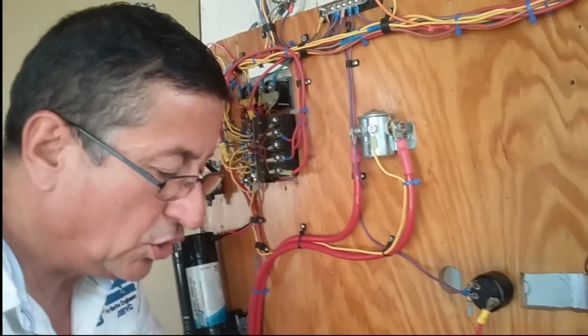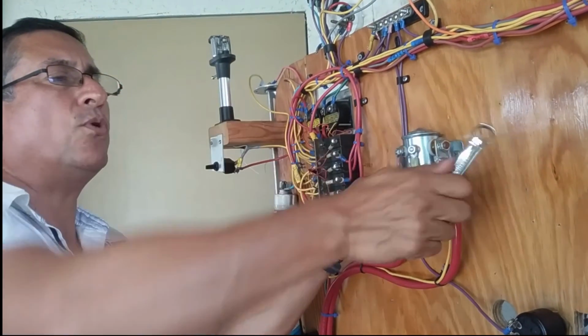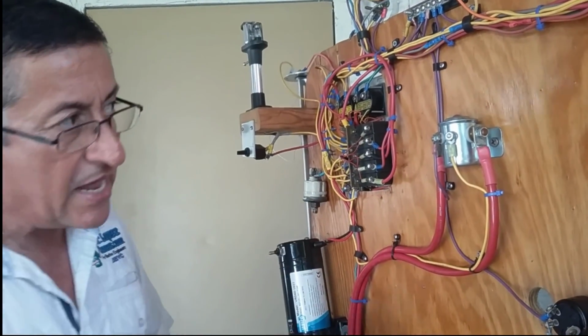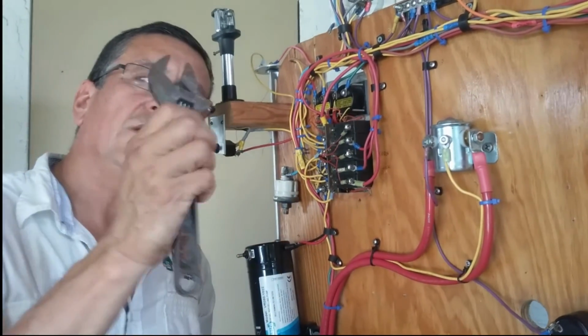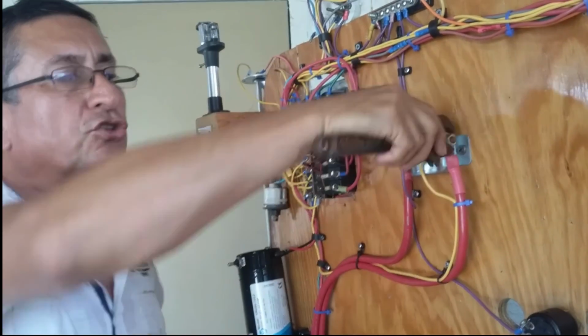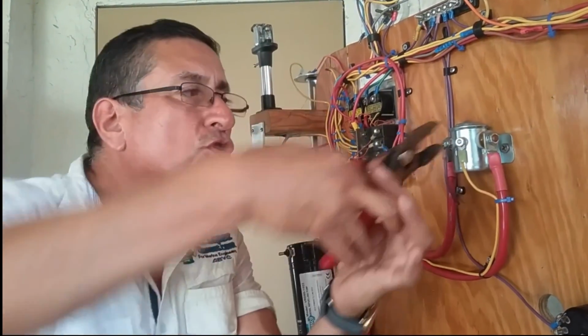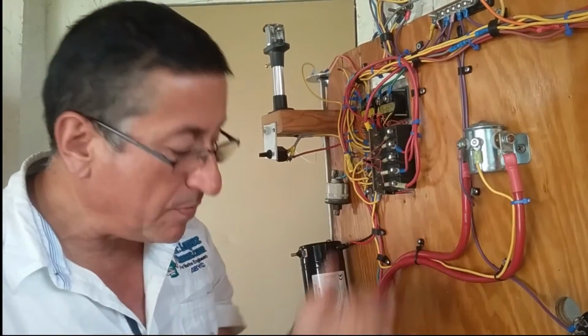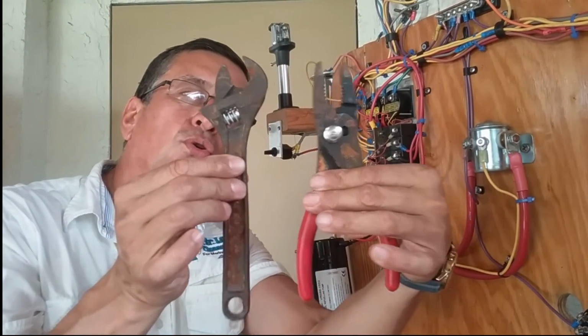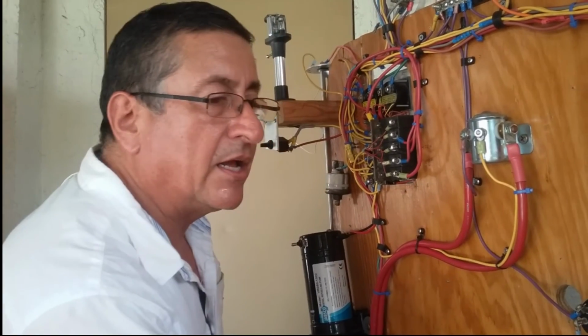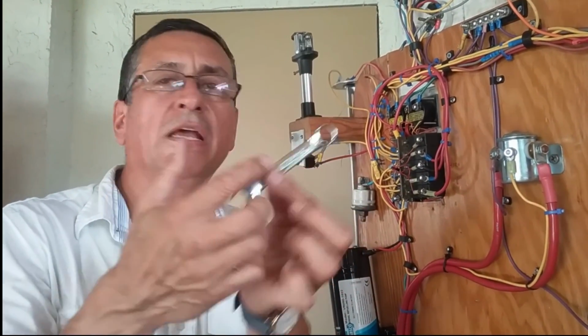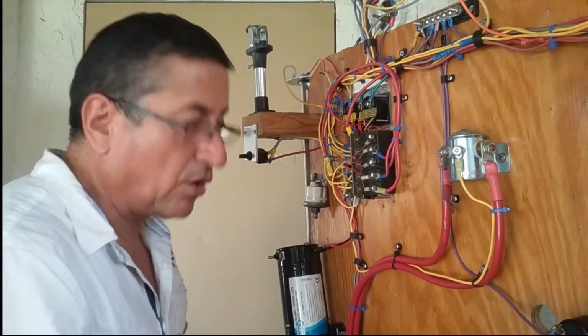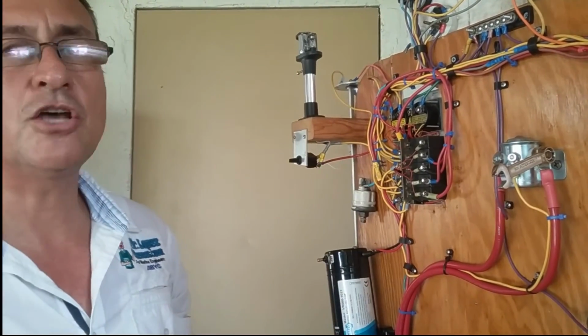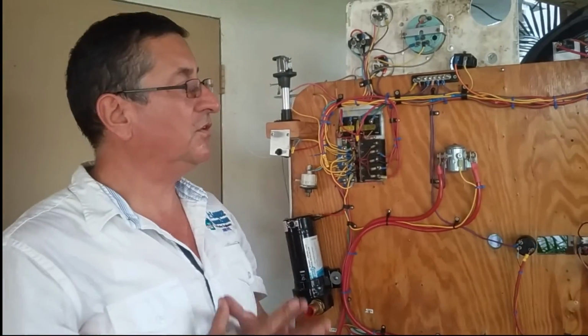Use appropriate tools. Use the proper wrench, the appropriate wrench. Never try to fix those terminals with adjustable wrenches. This is not good. You round the corners and damage the head of the bolt. And never try to use pliers like this to fix it, because you destroy the equipment. This is expensive equipment. Those tools are not appropriate. The only appropriate ones are the proper wrenches with the proper size, metric or standard, according to the head of the bolt. All right. Use appropriate tools. Use a hand screwdriver. Never use impact tools. This is the most important part.